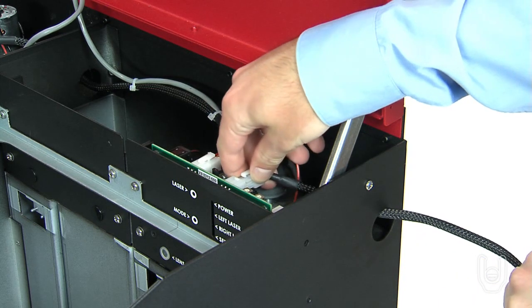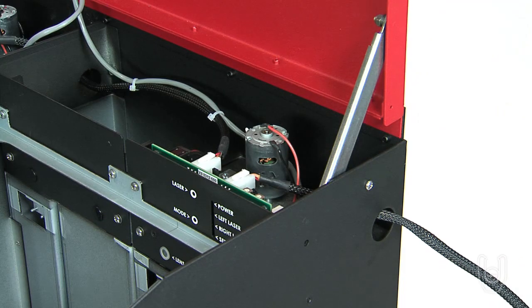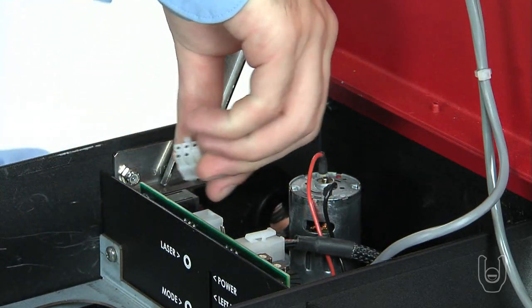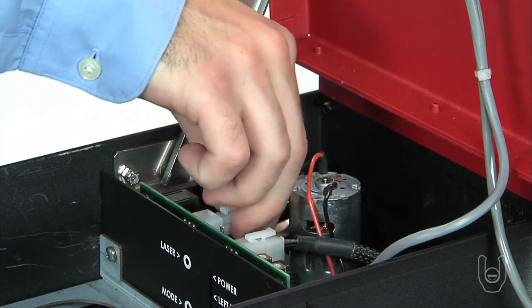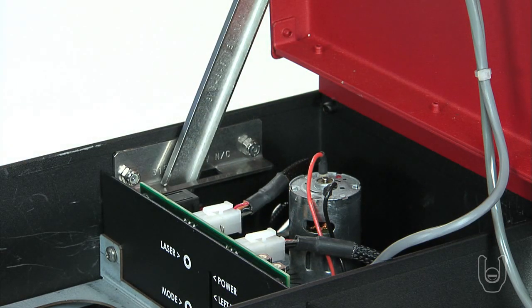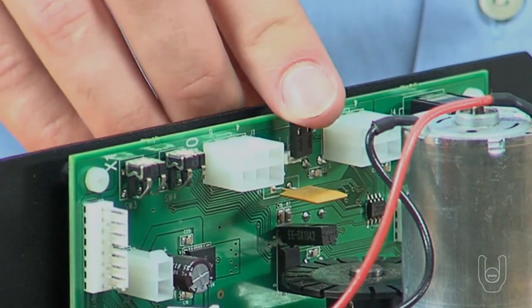Using the cabinet bus harness on the third motor controller board, insert one end through the grommet in the first cabinet and route it through the grommet in the next cabinet. Connect the 4-pin connector to the available adapter on the first motor controller board in the next cabinet. Repeat this process until all cabinets have been daisy-chained together. Confirm that the last motor controller in the series has a terminator jumper.